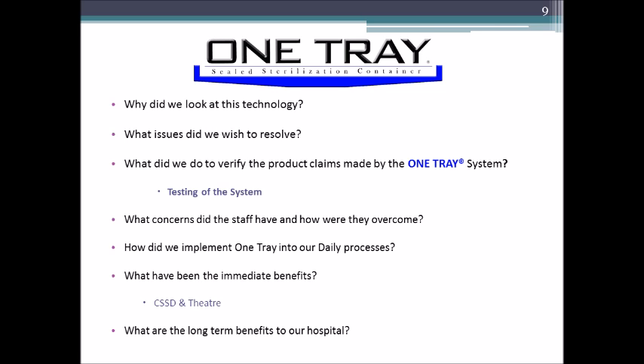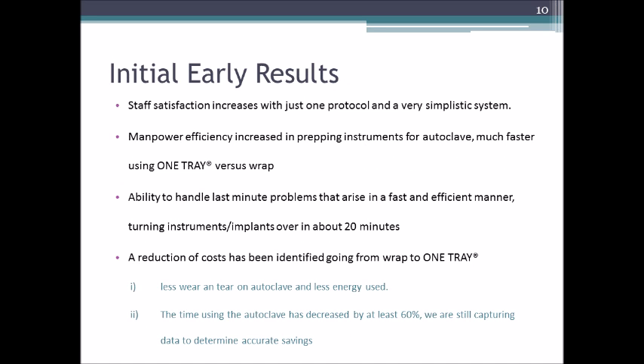I just know, for instance, my Getinge sterilizers in the hospital typically can use upwards of about 300,000 gallons of water a year. So there's a lot of water going down your drain for that 45-minute cycle to maintain that vacuum. So you can imagine the savings involved just from a processing standpoint. If we go over to the next page, there's a couple of more bullets. Some of the initial early results.